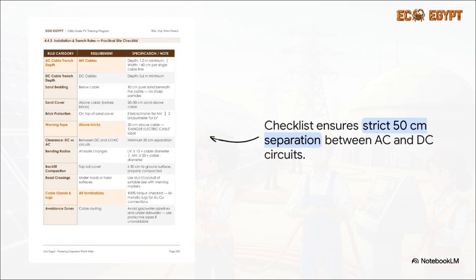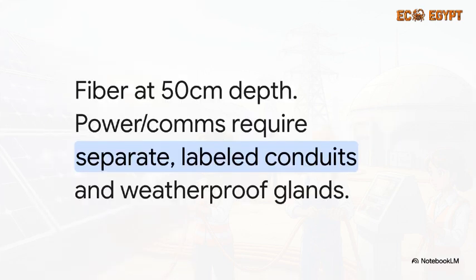It physically stops the powerful alternating magnetic fields of the AC circuits from interfering with or inducing harmful currents right into your DC lines. And of course, we literally cannot forget the brains of the operation, the SCADA and communication layout. These incredibly sensitive fiber optic data lines monitor every inverter, transformer, and breaker out there. Because they're so essential, they get their own dedicated routing rules to stay completely interference-free. That means separate, totally weatherproof, clearly labeled conduits, and a solid half-meter burial depth just to protect the delicate glass fibers inside from physical shock.